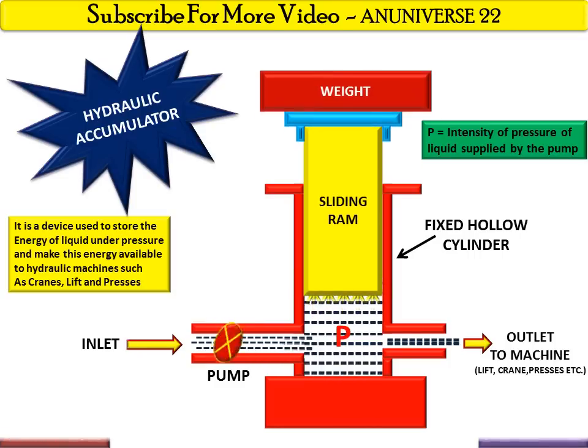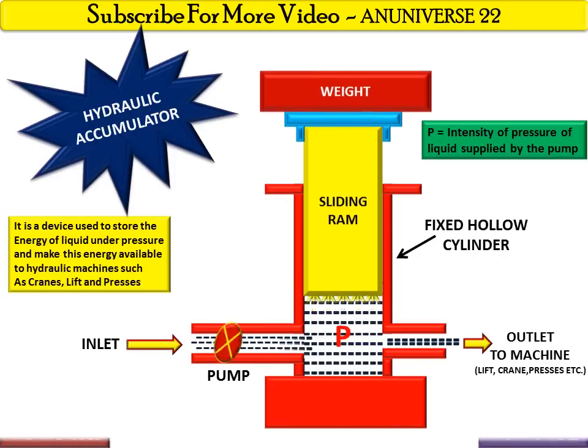But when the lift comes down, supply of energy is not required. Therefore the energy from the pump during this period — known as the idle period — is stored in the accumulator. The pump which supplies the liquid under pressure has to work continuously. Therefore an accumulator is placed between the pump and the hydraulic device in order to store extra energy during the idle period and supply the same during the working period.